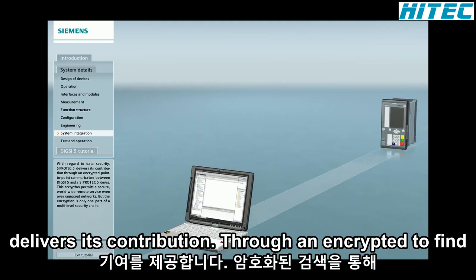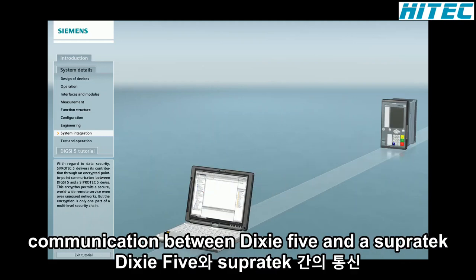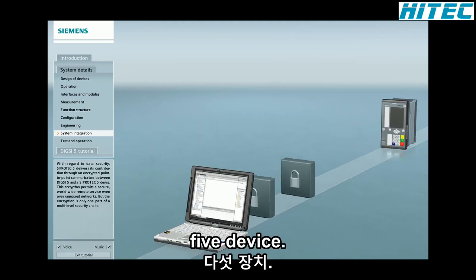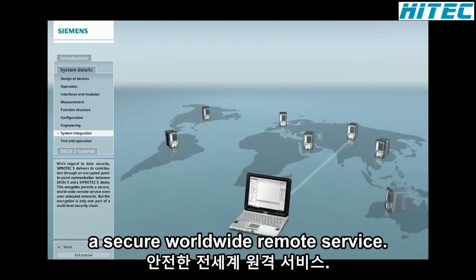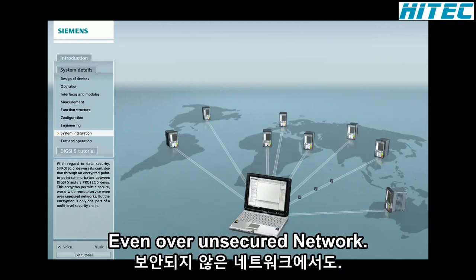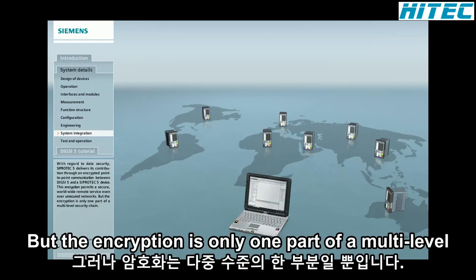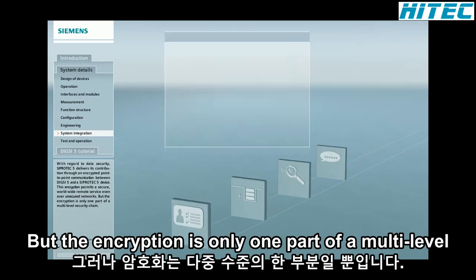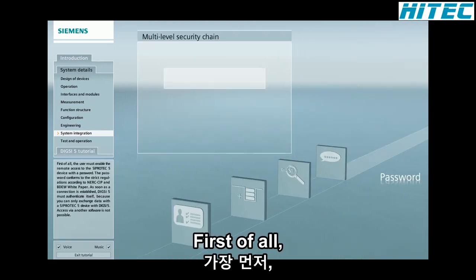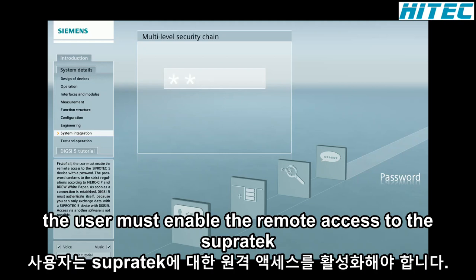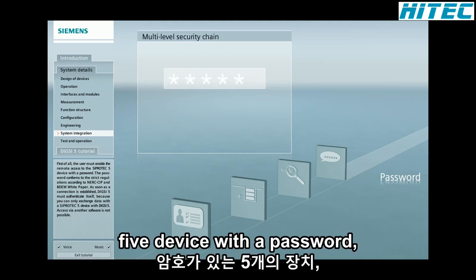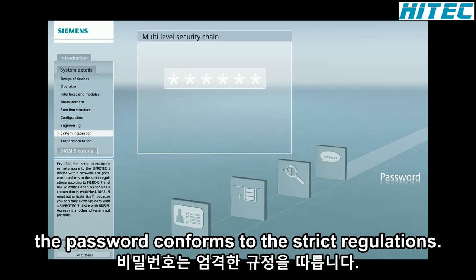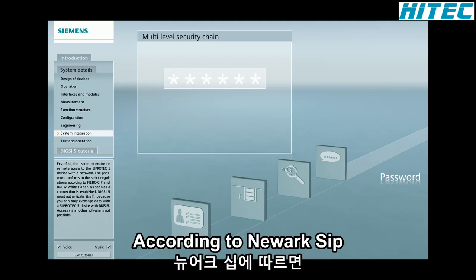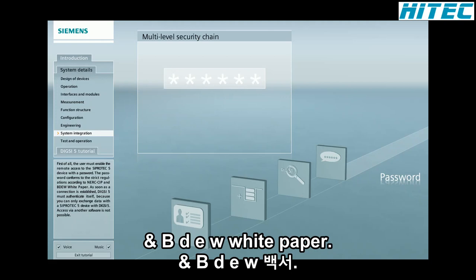through an encrypted point-to-point communication between DIGSI 5 and a SIPROTEC 5 device. This encryption permits a secure, worldwide remote service even over unsecured networks. But the encryption is only one part of a multi-level security chain. First of all, the user must enable the remote access to the SIPROTEC 5 device with a password. The password conforms to the strict regulations according to NERC-CIP and BDEW white paper.